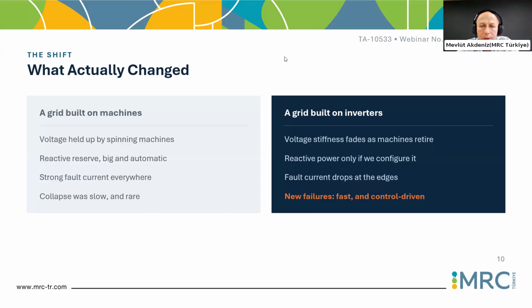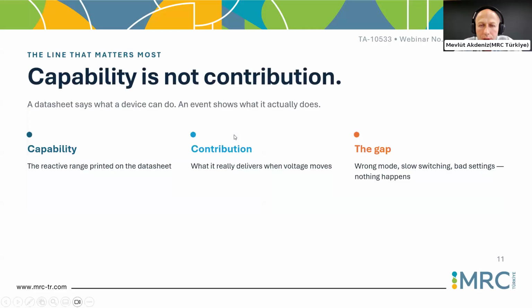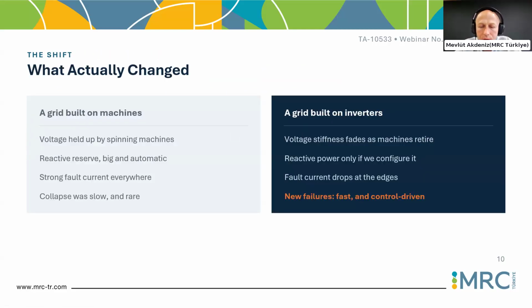So there are 2 very basic and fundamental differences and evolving shapes in our reactive power reserve regarding these emerging generation and loads. Moving from conventional synchronous generators to inverter-based generators makes plant and grid operation a bit complicated, because, as mentioned, a classical rotating machine has some natural response, like fault contribution or frequency response, some kind of damping torque or synchronizing torque in the grid.